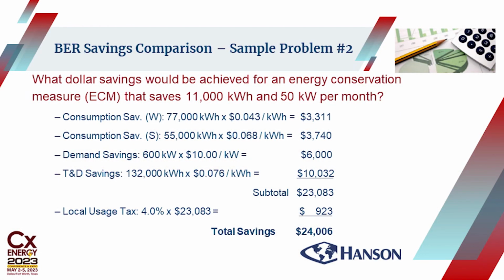So here's the question, and this gets into this later. What dollar savings would be achieved for an energy conservation measure that saves 11,000 kilowatt hours and 50 kW per month? So you've come up with a measure and you've calculated or projected that you're going to save 11,000 kilowatt hours in consumption, 50 kW in demand every month, 12 months a year. So if I do that with the incremental dollars, the rates that we talked about on the last one, I can crank through the calculations here: savings in winter, savings in summer, demand savings, transmission distribution, subtotal, tax. My total savings would be $24,006, but it took me a while to calculate that.